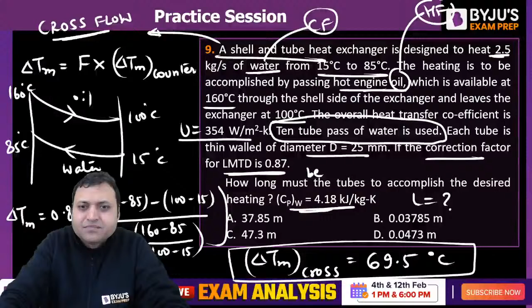What is the area? We can say number of passes into pi into d into L, into delta Tm, that is 69.5. N is equal to 10. The value of N will be equal to 10. So put the values: 2.5 into 4180 into 70 is equal to 354 into 10 into pi into diameter. What is the diameter? Diameter is 25 mm. So 0.025 into L, which is unknown, into 69.5.